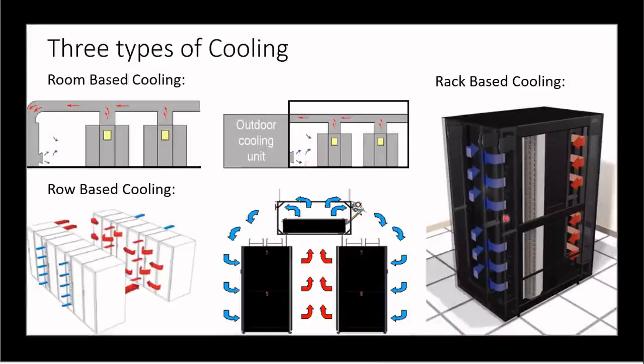This also depends on the customer's requirement. Room-based cooling is cheaper, but it does not provide better efficiency because we don't know where the hotspots are. Row based cooling is better compared to this, but it also increases cost. Rack based cooling is even better because it focuses on a single rack, so there are fewer chances of hotspots. But it also depends on the type of data center, small or large, and what the customer needs.